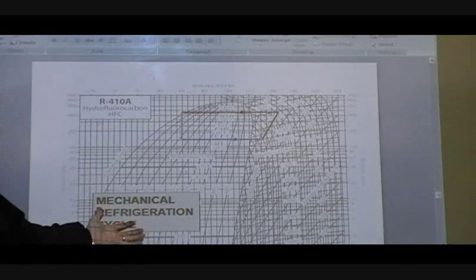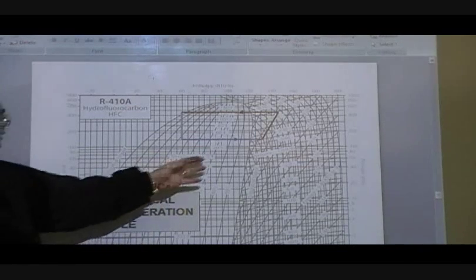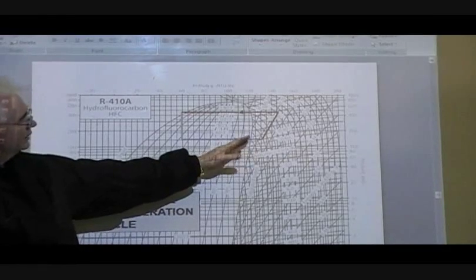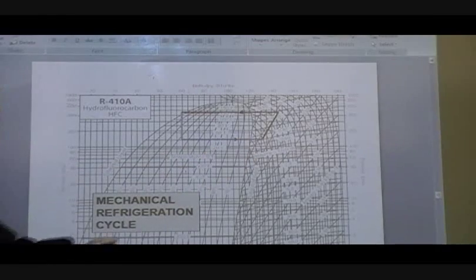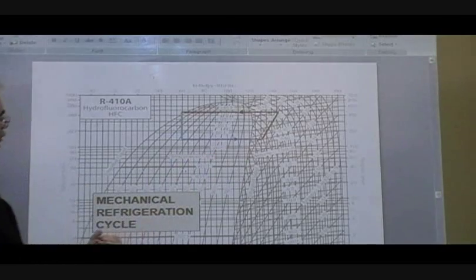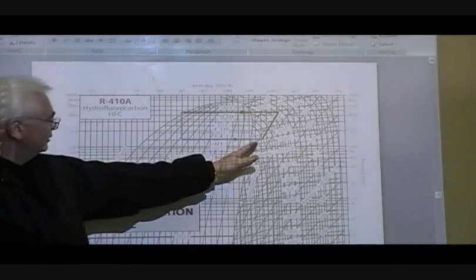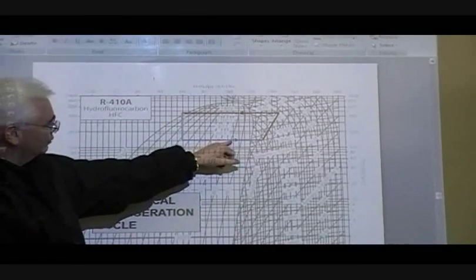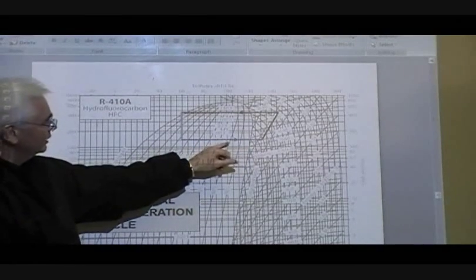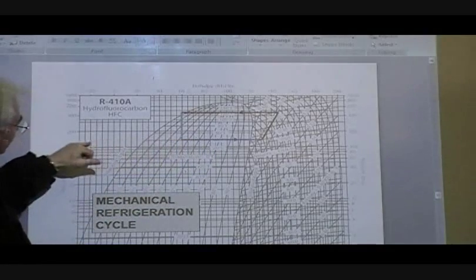Let's say in this scenario you've got 10 degrees of superheat. Your suction line coming off the evaporator is going to be about 50 degrees if you measure it with a thermometer. You've got a 50 degree suction line coming off the evaporator, you've got a 40 degree saturated vapor temperature. How do you know that? By your pressure.